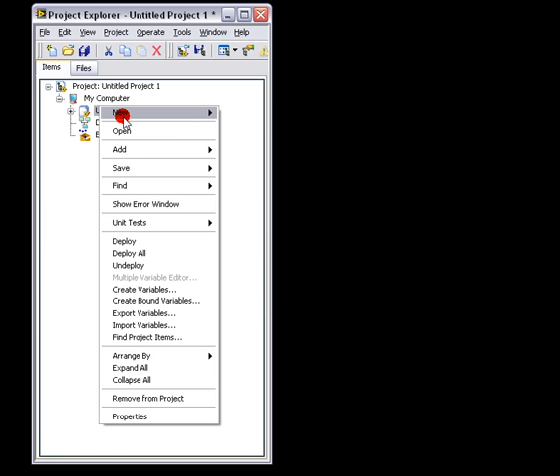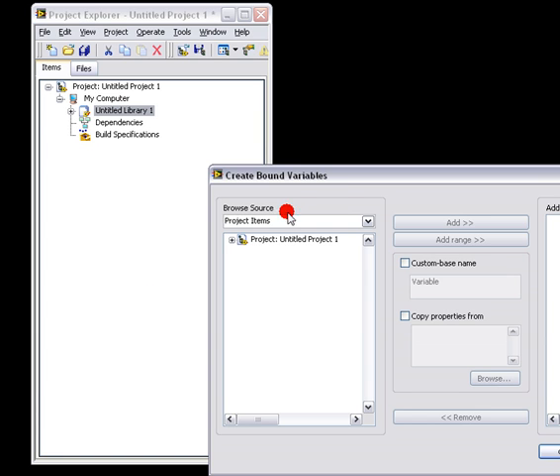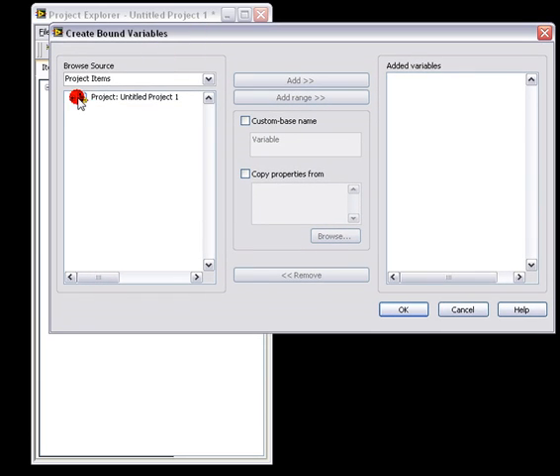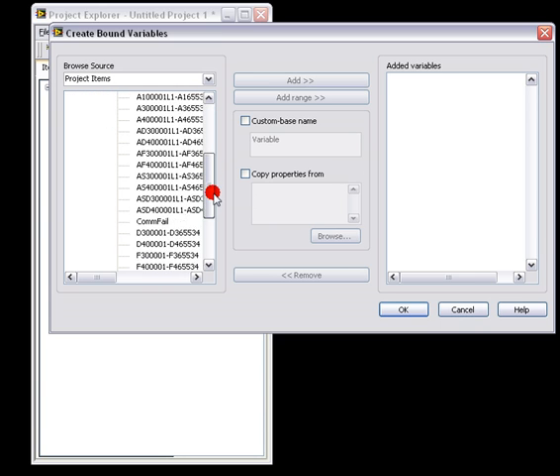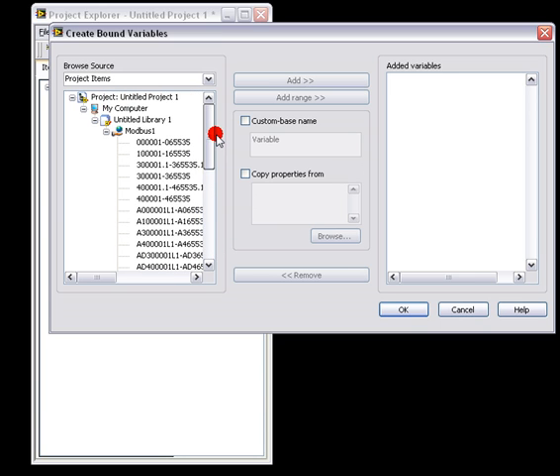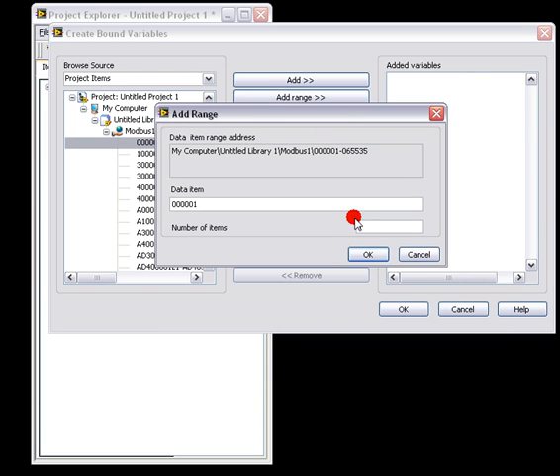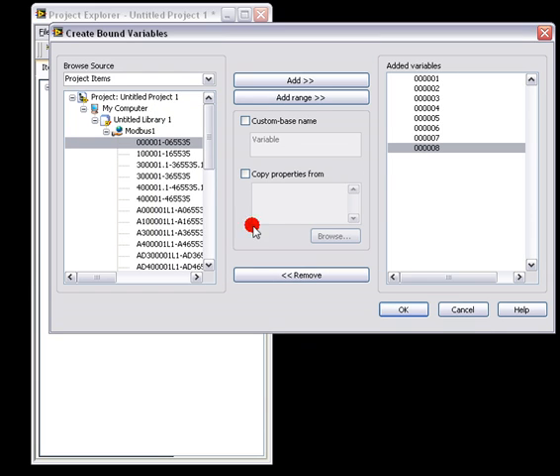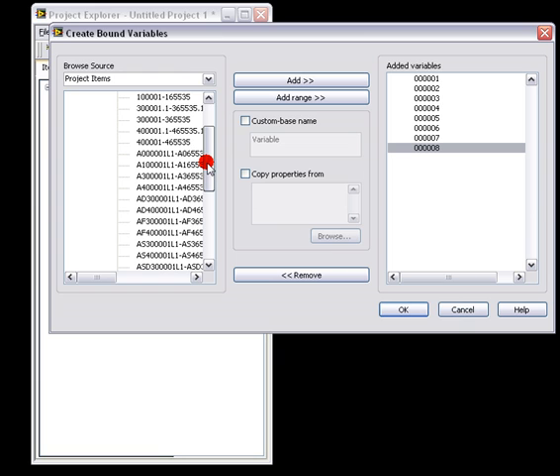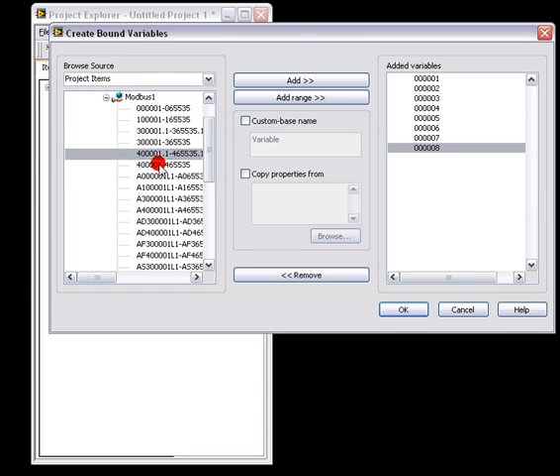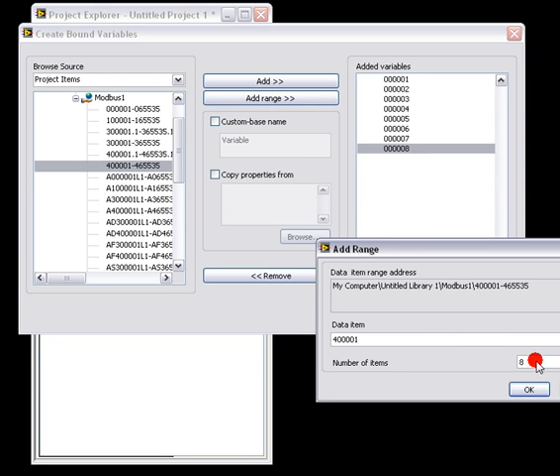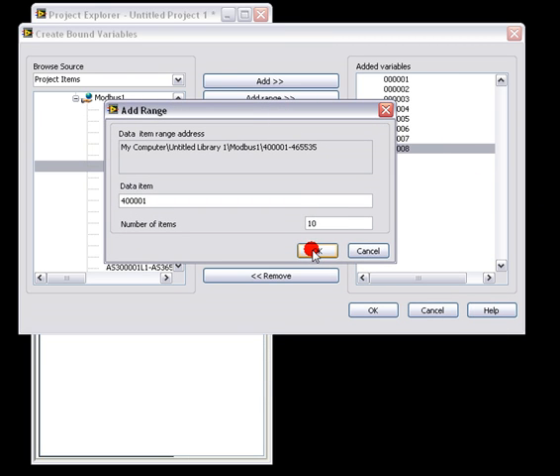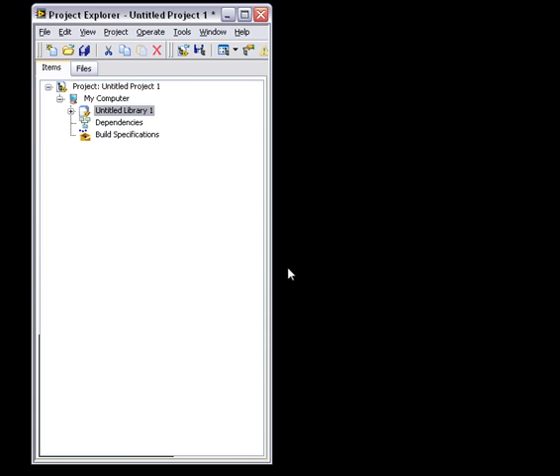And then we will need to create bound variables to our library. And since that library is a Modbus master, we're presented with a wide variety of options of Modbus registers here. Control ports 1 through 8 have been mapped to coil inputs, so we're going to add those. We're going to add 8 of them, of course. Our MB array that we set up in CRBasic editor are mapped to registers 400001 through 400010. So we'll add that because we had a 10 element array in our program. So I'm going to add 10 and select OK. Now we'll say OK. It's configuring.